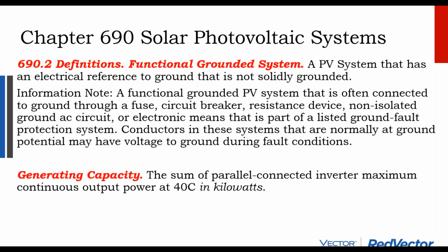But how DC really works is you have your positive side and your negative side, and on that 12-volt battery, you have 12 volts of potential between the two. And so if you don't connect your negative to ground, you still have 12 volts between your positive terminal and your negative terminal. It's just now that negative terminal does not have a direct reference to ground. And so the problem with negatively grounded systems is that it creates a blind spot in the ground fault detection. In very limited circumstances, you could have a ground fault on a negatively grounded system that is not detected by the inverter system itself.